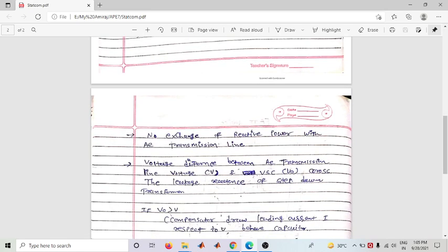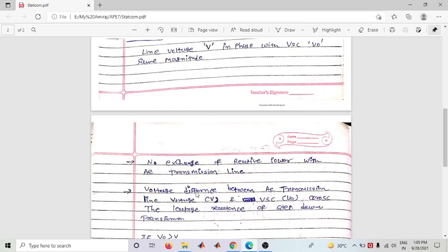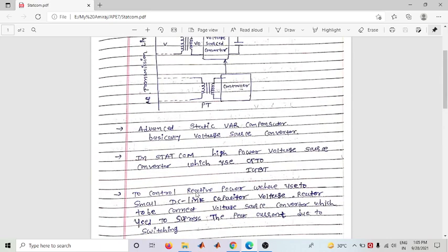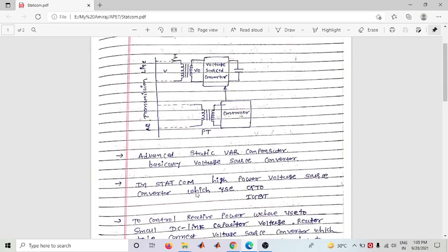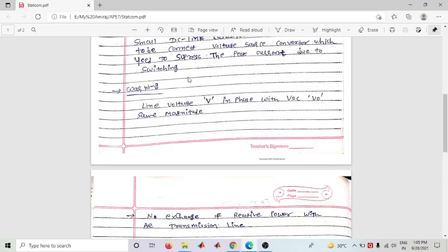However, when there is a voltage difference between the AC transmission line voltage and the VSC output voltage V0, this difference appears across the leakage reactance of the step-down transformer. So the leakage reactance of the transformer plays a key role when a voltage difference exists.